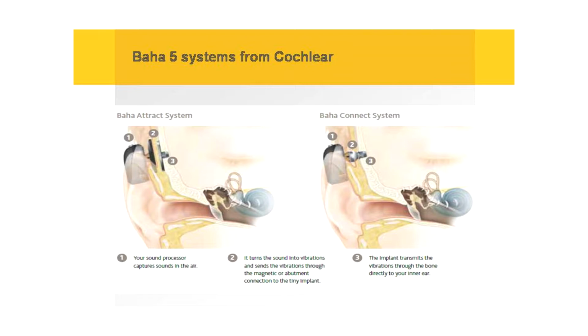Number one, the sound processor, which is worn on the bone behind the ear, captures the sounds and turns those into vibrations. Number two is the transmission across the skin and soft tissue, whether by the magnetic connection or the abutment connection. And number three is the implanted implant, which then sends the vibrations through the bone of the skull to the cochlea.